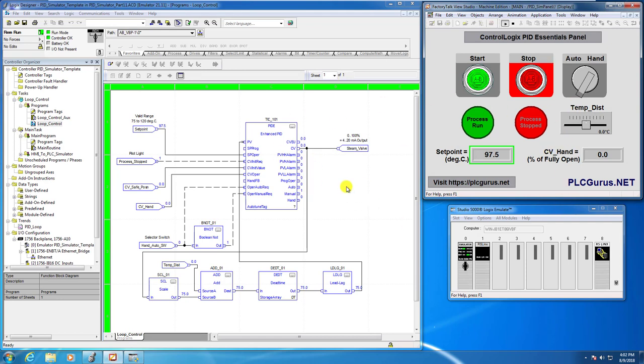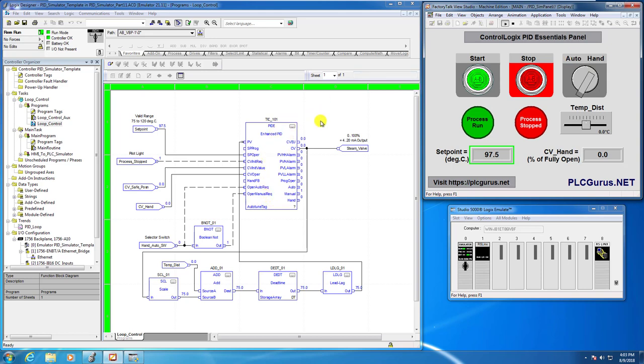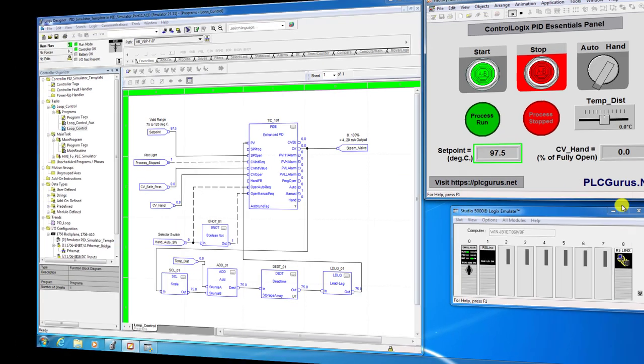In the last video, we got everything connected and started performing some open loop tests in hand mode. We noticed that everything worked as expected — the dynamic response to a change in our CV, our PV followed it immediately because we have a theoretical perfect process with zero dead time and zero lead lag time. But when we hit it with a slight temperature disturbance in auto or closed loop feedback mode, the controller went into instability almost immediately and oscillated uncontrollably. So let's reproduce that and then do a brute force approach to manual tuning.